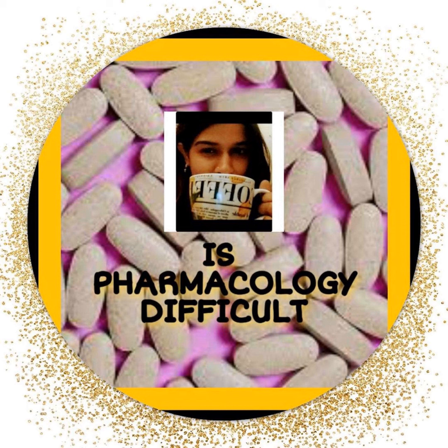Now the next question, what to report? Any type of adverse event, whether it is known, unknown, serious, non-serious, rare, common, frequent, any kind of adverse event related to the medical devices can be reported. How and whom to report? The medical device adverse event reporting form is available at ipc.gov.in, and the research associates from the medical device adverse event monitoring centers fill this form and submit it to the National Collaboration Center, that is SCTIMST.